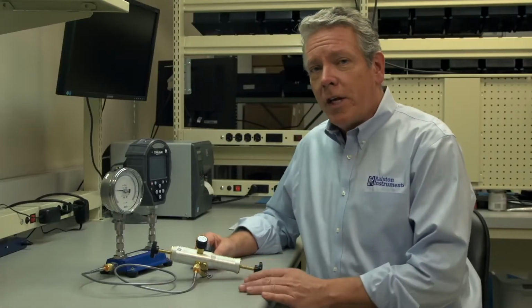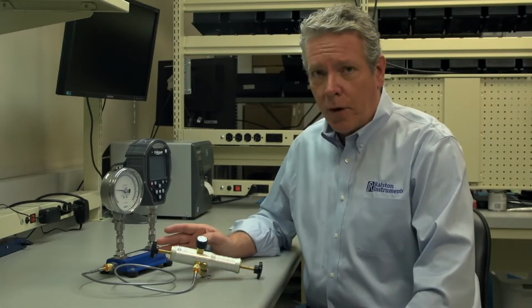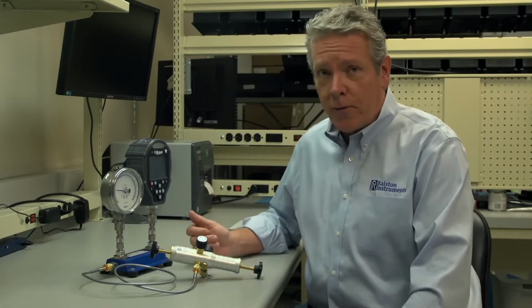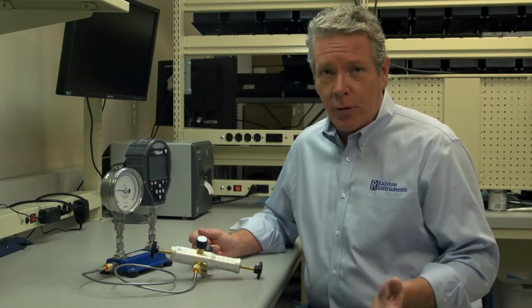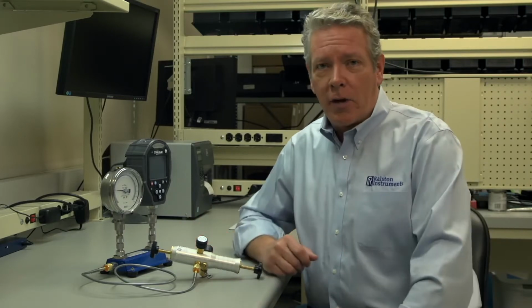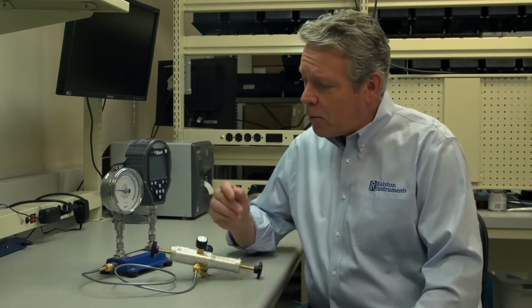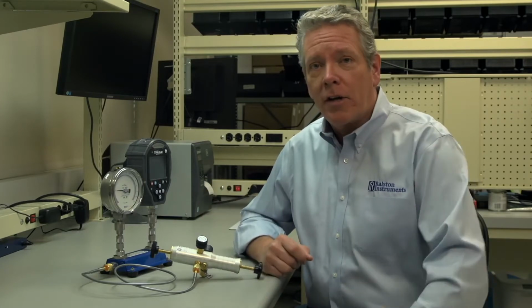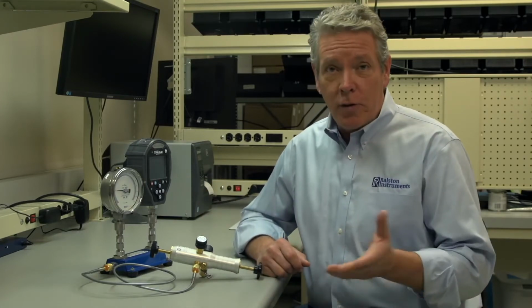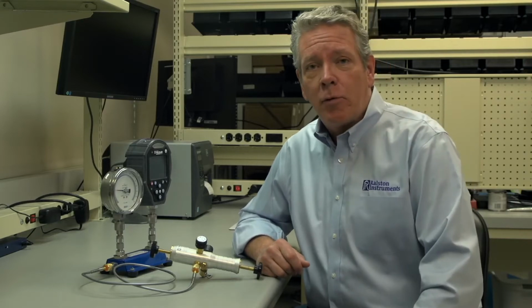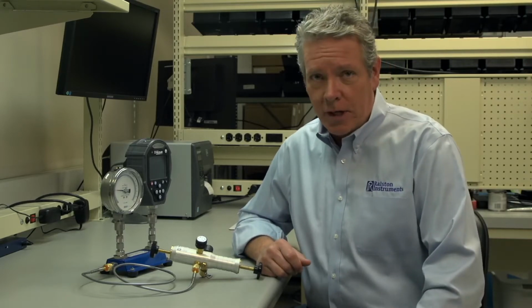Now you may have noticed we're setting the DUT to the cardinal point and reading the actual pressure on the FieldLab, which is the reverse of a typical test. This provides greater accuracy since you're not guessing which hash mark the needle is closest to on analog gauges and then estimating hundredths or even tenths, which could mean the difference between a passed or failed DUT.